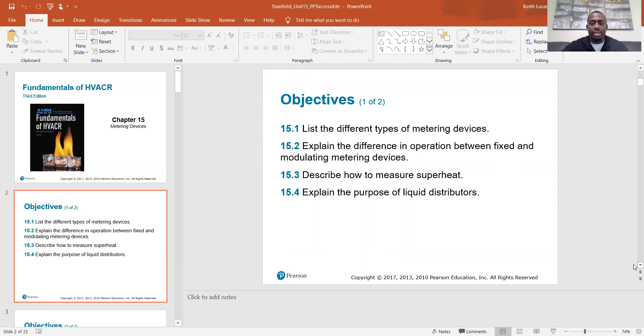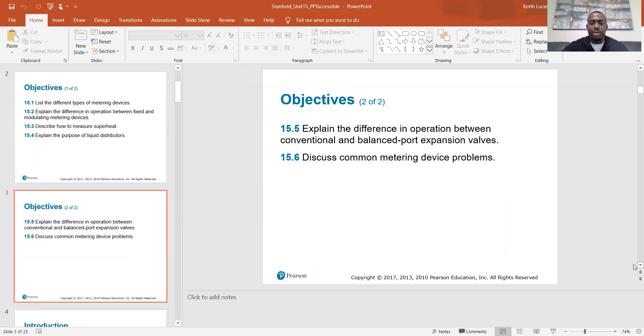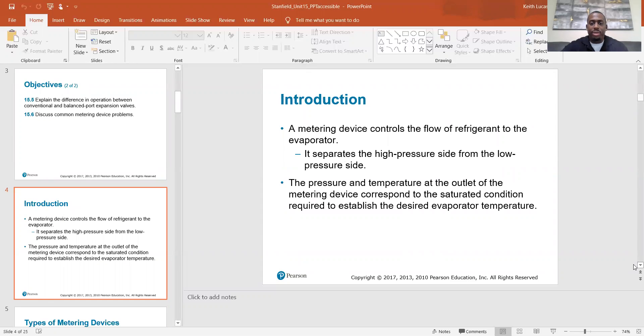Chapter 15 objectives: list the different types of metering devices; explain the difference in operation between fixed and modulating metering devices; describe how to measure superheat; explain the purpose of liquid distributors; explain the difference between conventional and balanced port expansion valves; and discuss common metering device problems. A metering device controls the flow of refrigerant to the evaporator and separates the high pressure side from the low pressure side. The pressure and temperature at the outlet of the metering device corresponds to the saturated condition required to establish the desired evaporator temperature.